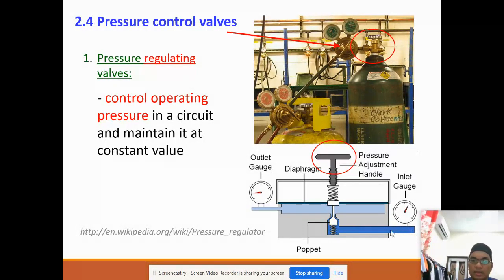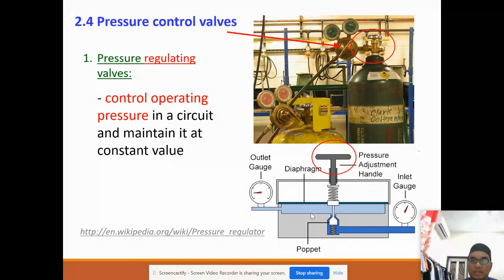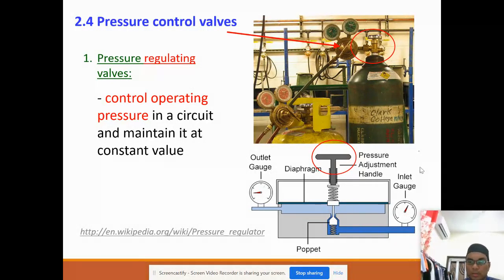When we supply the air, we can control at what Pascal level the pressure should be. The poppet valve will open and the pressure will go through to this outlet. There is a pressure adjustment handle to control the level of the air from the tank to the outlet. With these two gauges, we can control the inlet and also the outlet pressure.